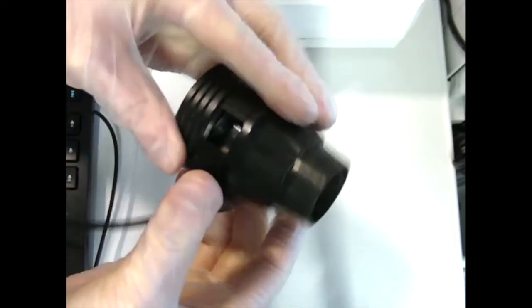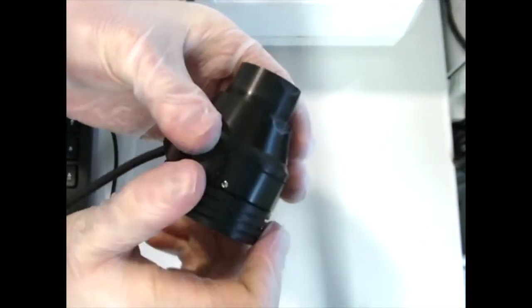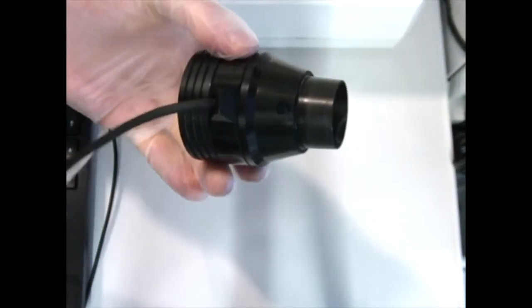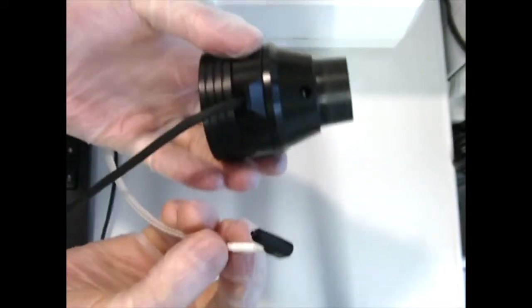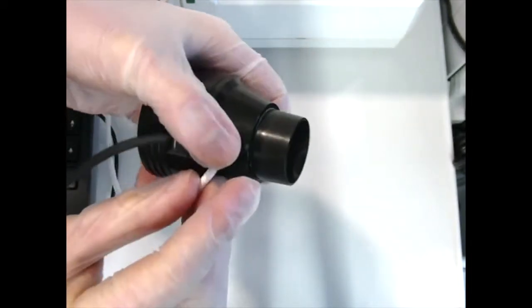This horseshoe shape cable clips inside to the housing, and this is what detects how fast the turbine is turning inside, and thus can measure expired air volume. There's also a hole for the sample line to sit, and this is what samples the expired air during exercise.